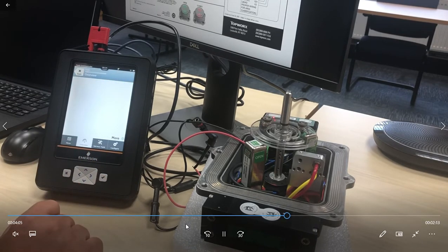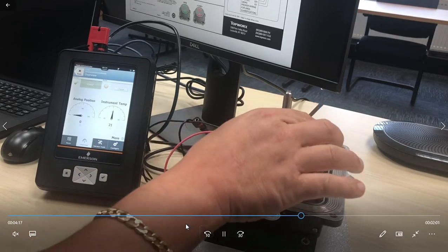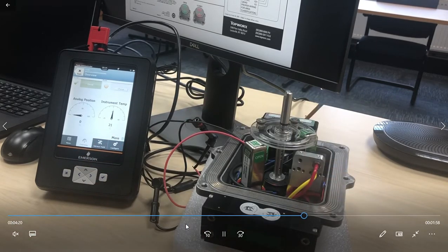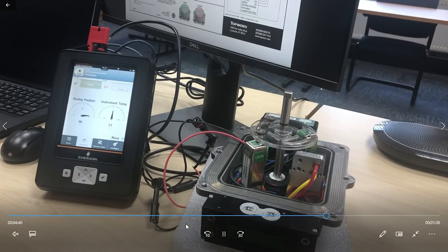And now if we look at the dashboard on the device, again, because what we need to do is poll the information from the device and back again, there is a small lag in timing, just so that the information can be received, registered, and inputted on the device. And within Foundation Fieldbus, this is limited to the speed at which the Foundation Fieldbus connects and transmits the information. But generally speaking, for the applications that this is used in, it's not an issue. And this is only a demonstration of the capabilities.